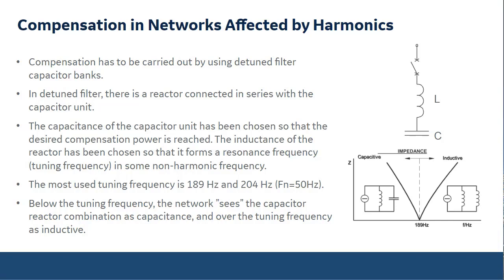So inductive capacitor bank and inductive transformer winding, they cannot make any resonance. So this is now safe to put this kind of capacitor there, and you don't have to worry about the harmonics or worry about the resonances if you put the reactor on top of a capacitor in there.